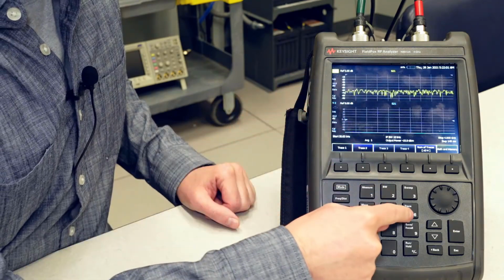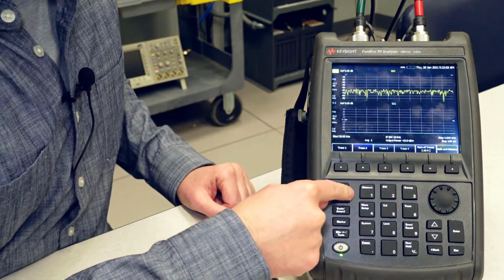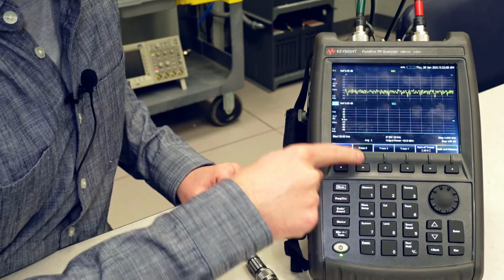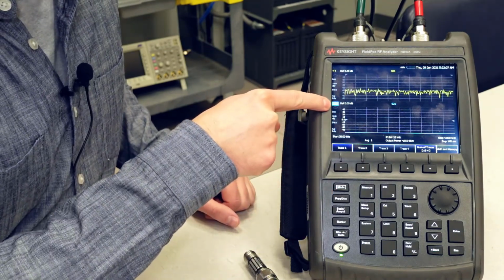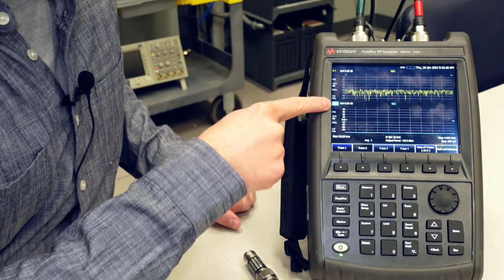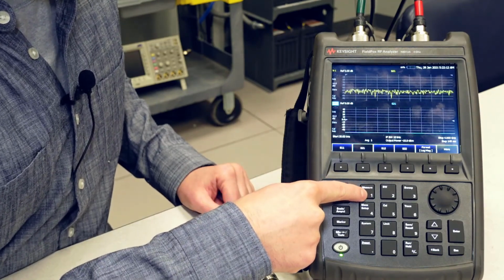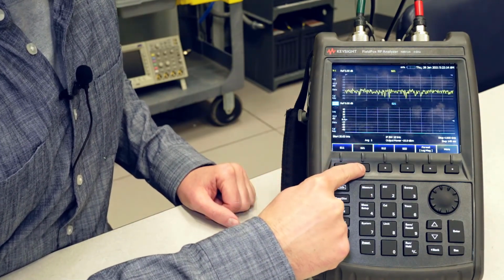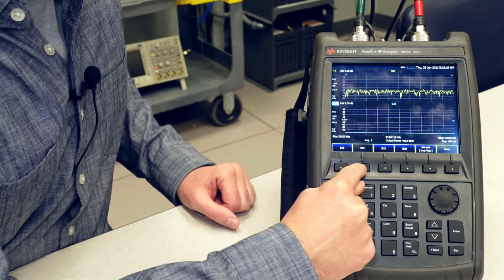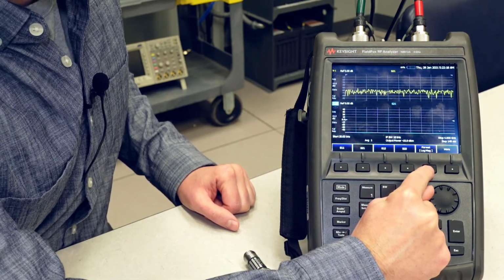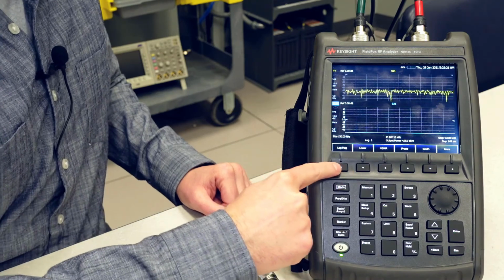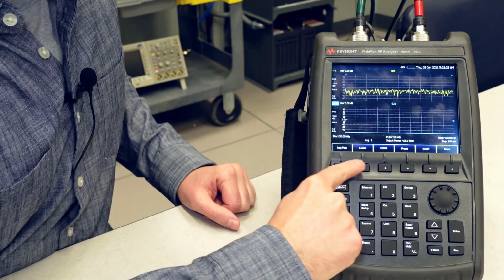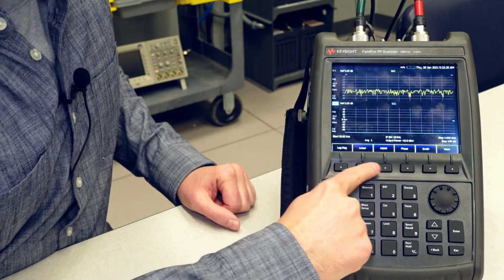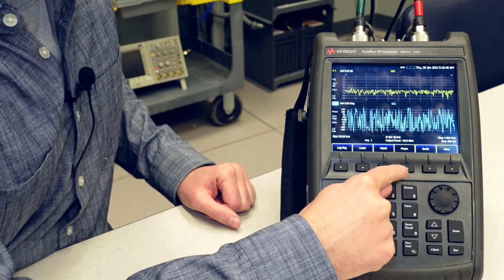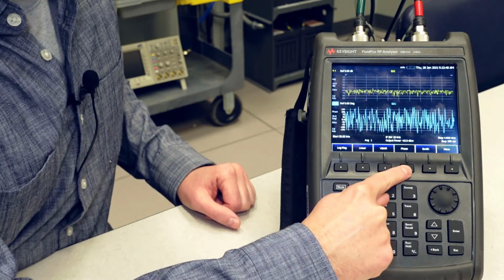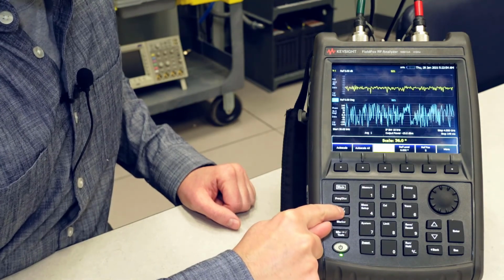Now let's move down to trace 2 and format that one by selecting trace, trace 2, and you can see that it's highlighted now, meaning that's the active trace. Under measure, we can confirm that it's also set to S21, and under the format, we can change it from logarithmic magnitude, which was the default format, to phase. And you can see some of the other options that we have here, but for this discussion, we're going to keep to phase. And then back to scale.